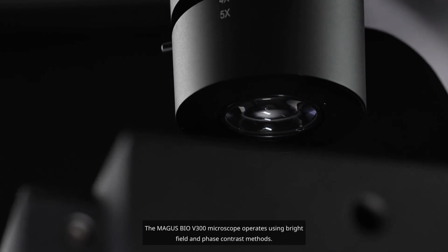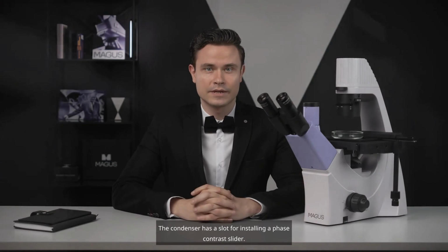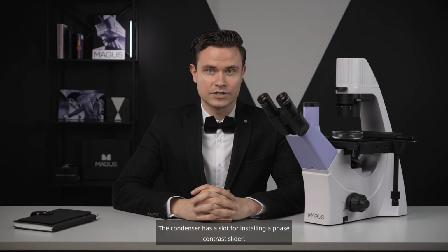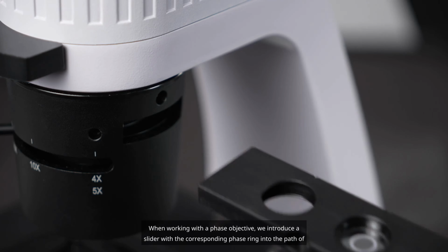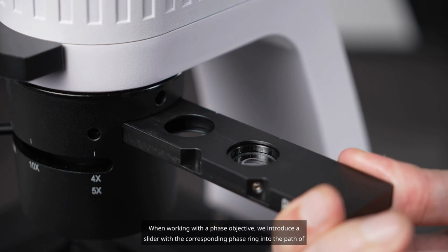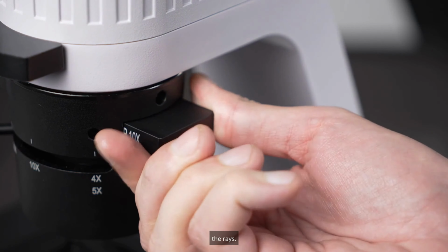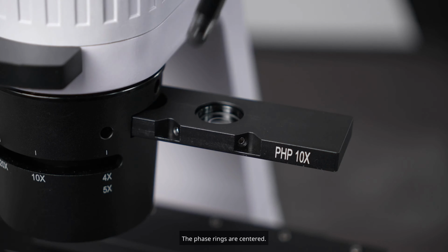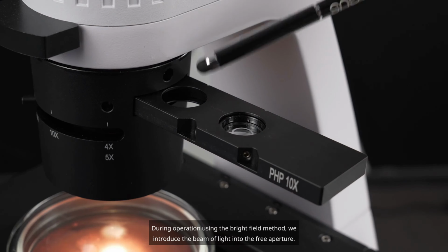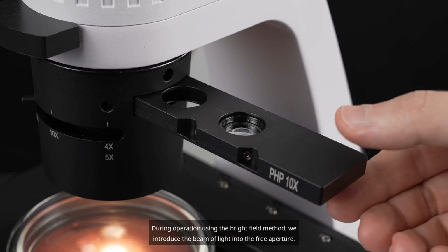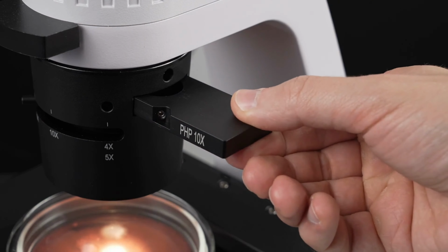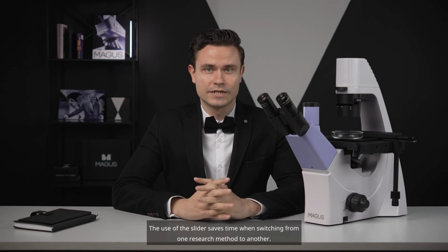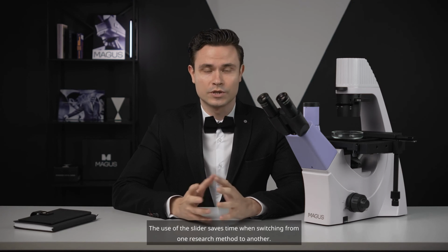The MAGUS Bio V300 microscope operates using bright field and phase contrast methods. The condenser has a slot for installing a phase contrast slider. When working with a phase objective, we introduce a slider with the corresponding phase ring into the path of the rays. The phase rings are centered. During operation using the bright field method, we introduce the beam of light into the free aperture. The use of the slider saves time when switching from one research method to another.